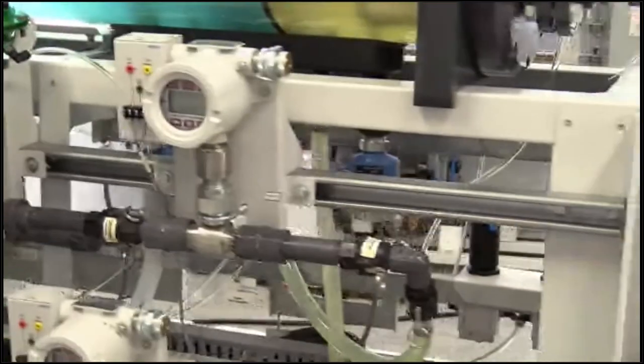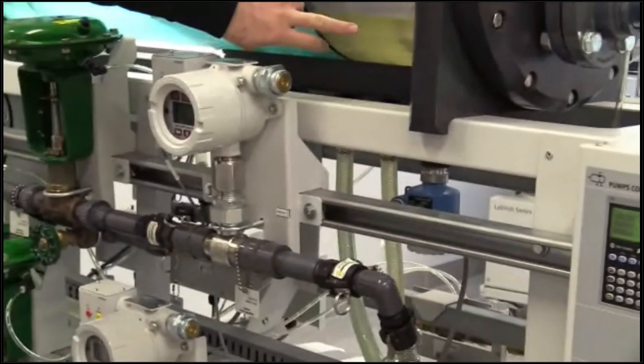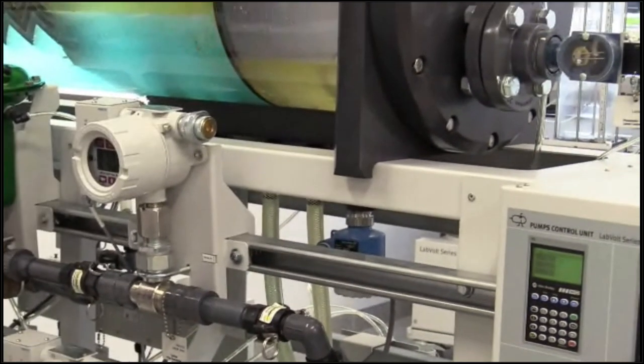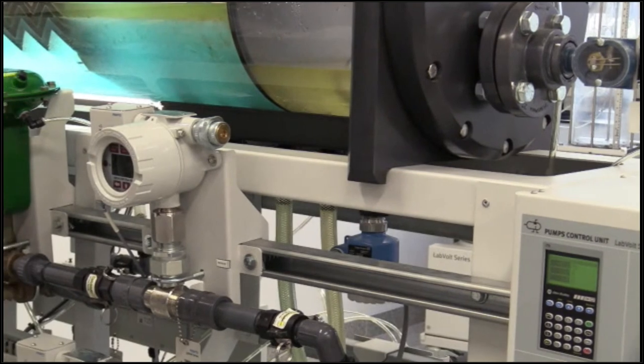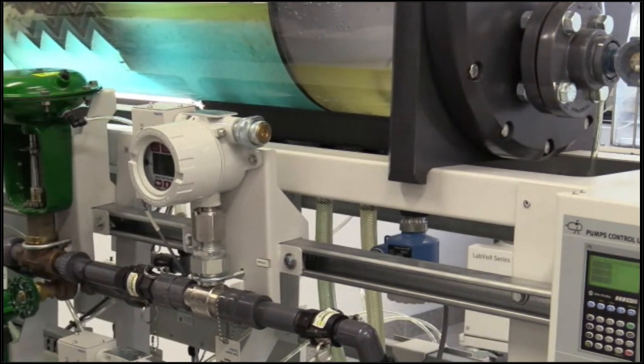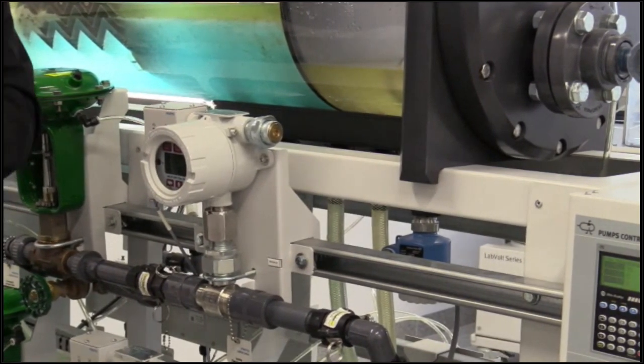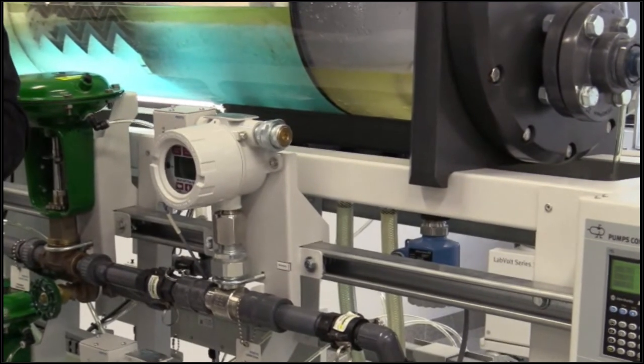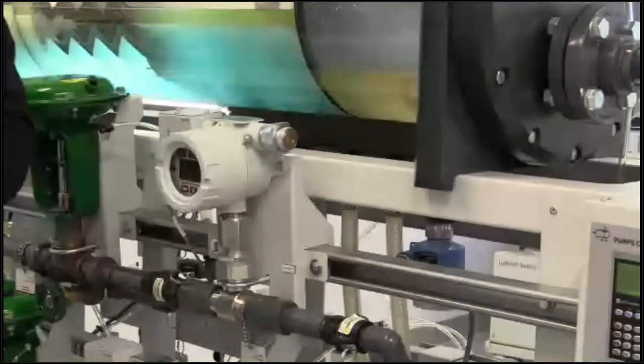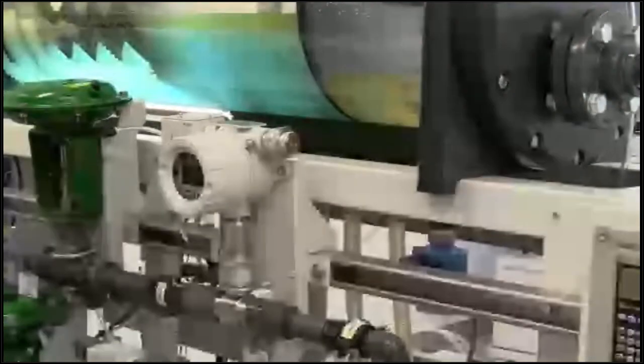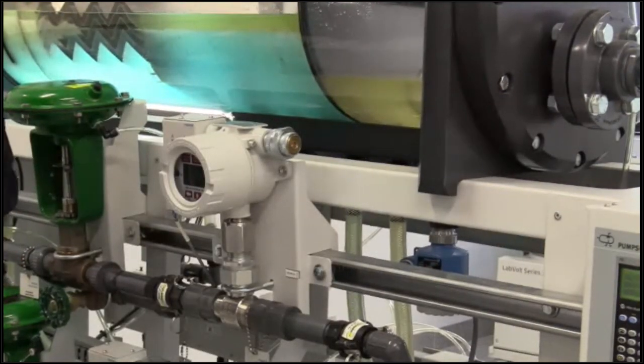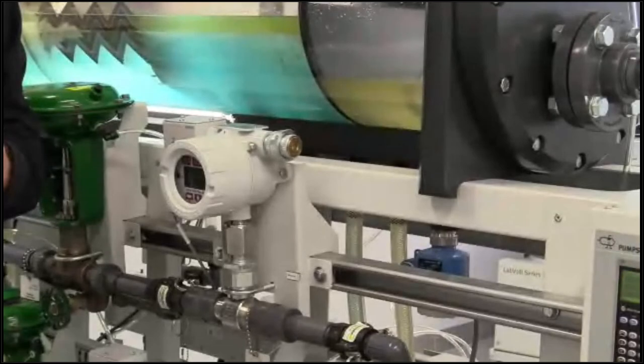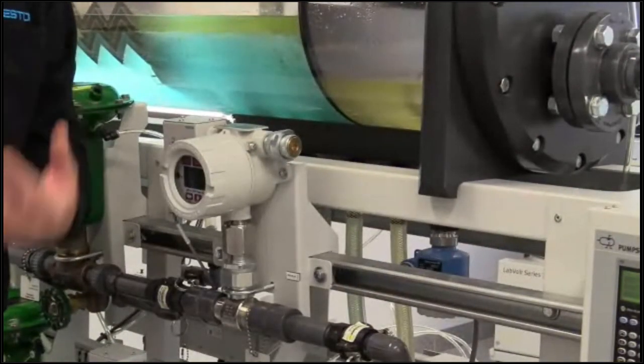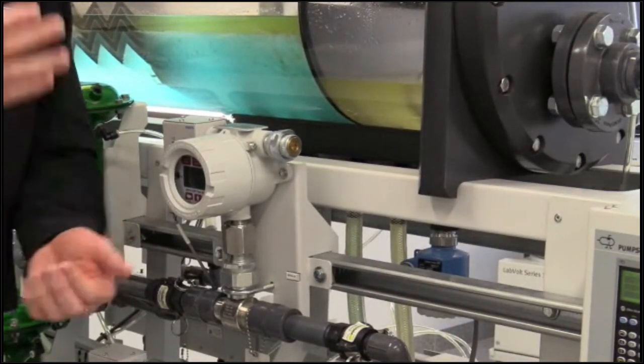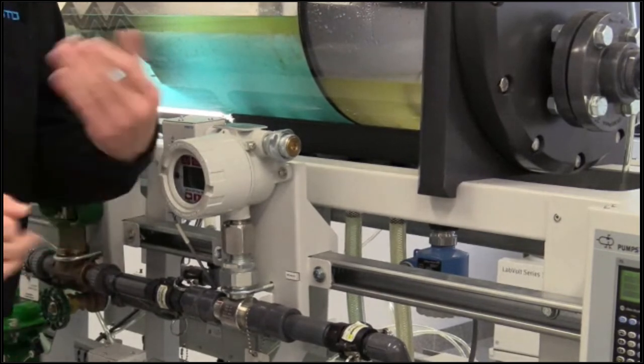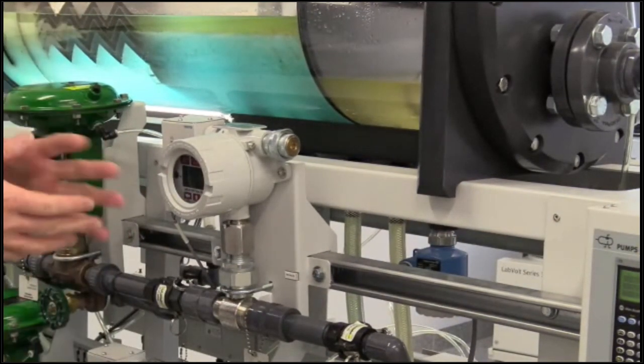But here, hopefully we can see it in a moment, we have a vortex breaker. So we have the hole where the hose goes down, and we placed two baffles 90 degrees on top of it. Because when the oil is dripping down, it's going to create a little whirlpool and may suck some gas in. So we did not separate the gas from the oil. So we're going to cut this whirlpool with this mechanical element.